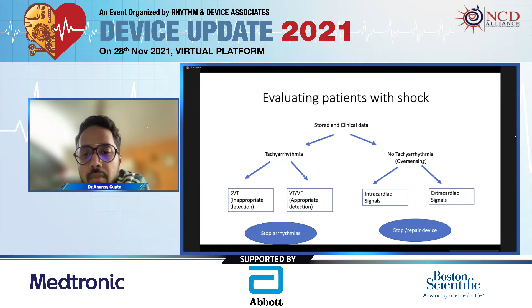While if there is no tachyarrhythmia, then likely due to oversensing the patient is receiving inappropriate shocks. It can be due to intracardiac signals or extracardiac signals. In those cases we have to stop those extracardiac or intracardiac signals from happening, and even the device can require repair.